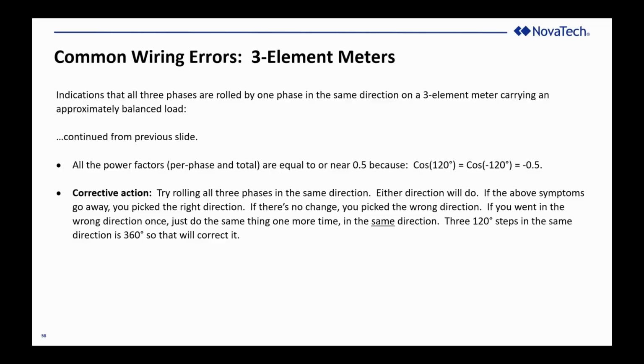So if they were wrong to begin with because they were rotated one phase in the wrong direction, and you rotated a second phase in the wrong direction, and that didn't correct the problem, rotate it one more step in the same direction, and you've gone 360 degrees, you've corrected the problem. One step might have a fix, two steps, definite fix for the wiring error.